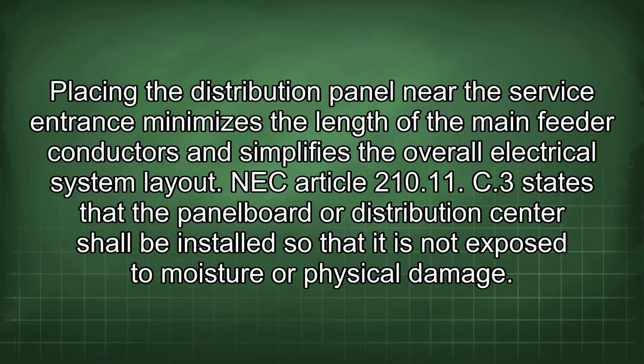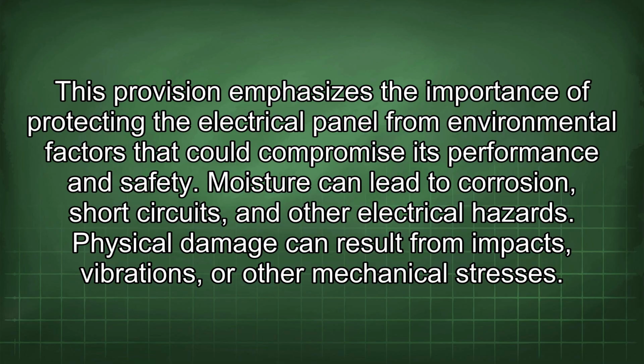C3 states that the panel board or distribution center shall be installed so that it is not exposed to moisture or physical damage. This provision emphasizes the importance of protecting the electrical panel from environmental factors that could compromise its performance and safety. Moisture can lead to corrosion, short circuits, and other electrical hazards. Physical damage can result from impacts, vibrations, or other mechanical stresses.